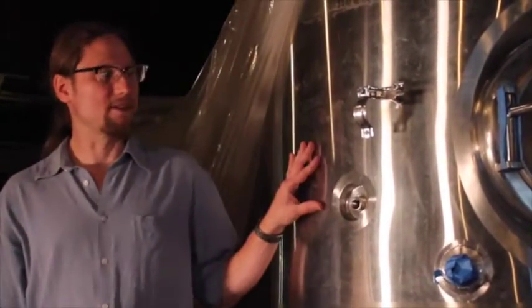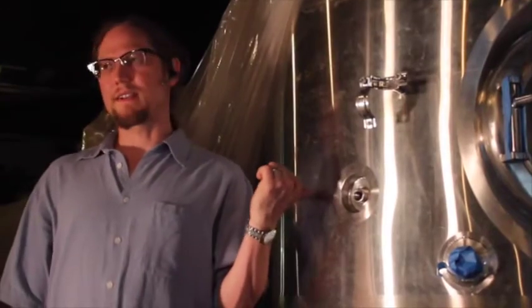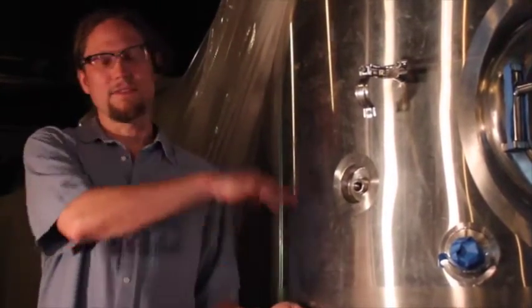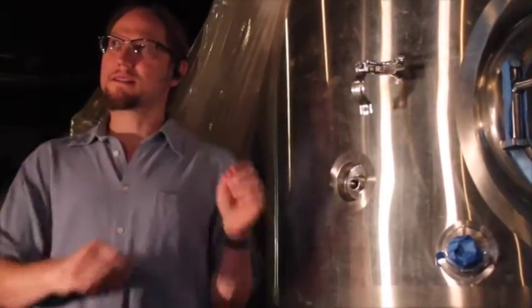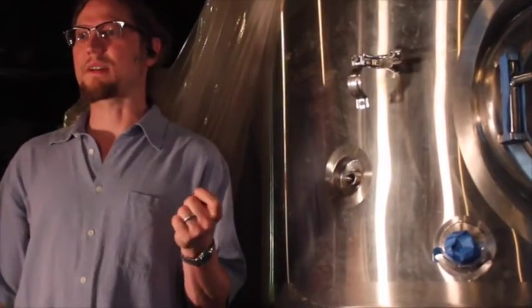Here we have a typical thermowell. It's welded inside of this fermenter. It protrudes inside the tank far enough so that when the tank is filled with liquid, the end of the thermowell is at the same temperature as the liquid that surrounds it.